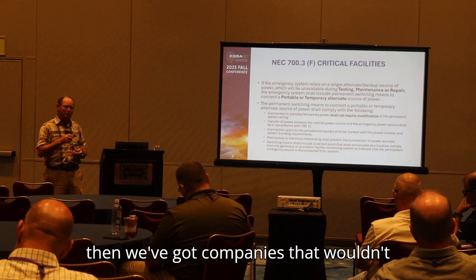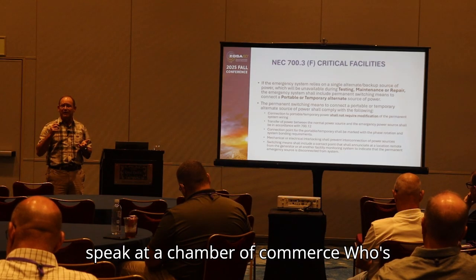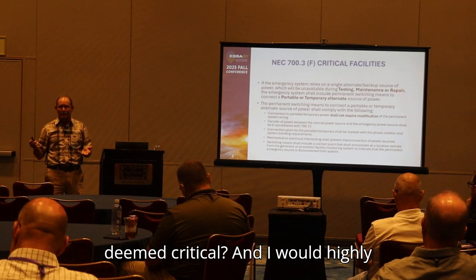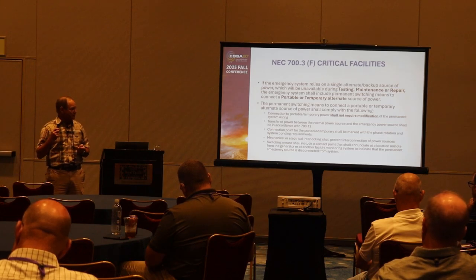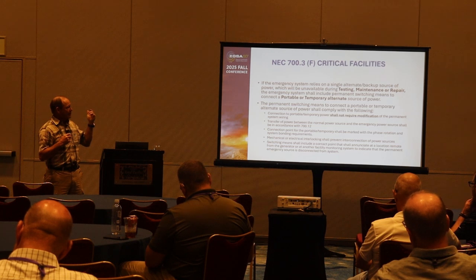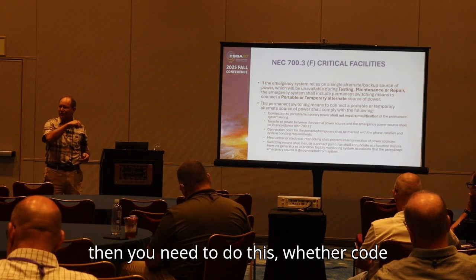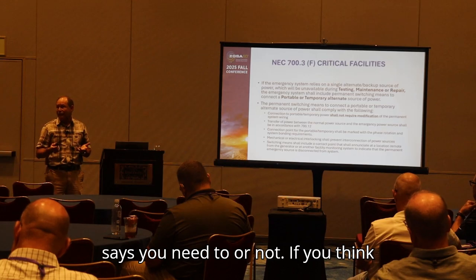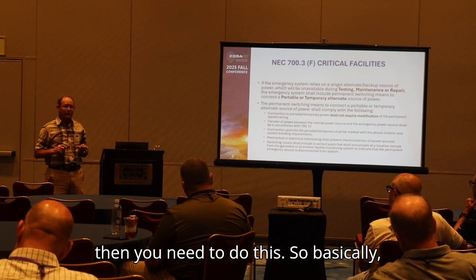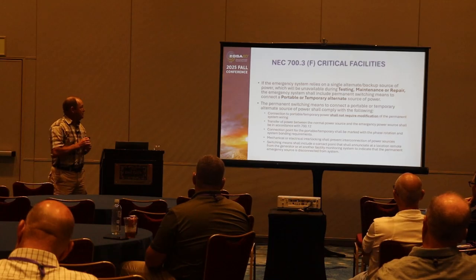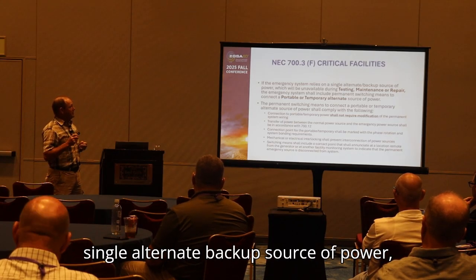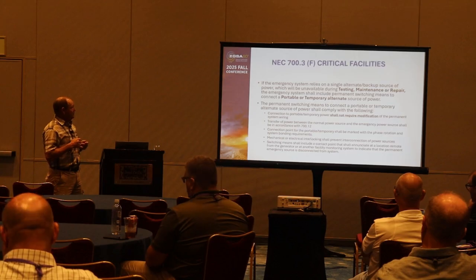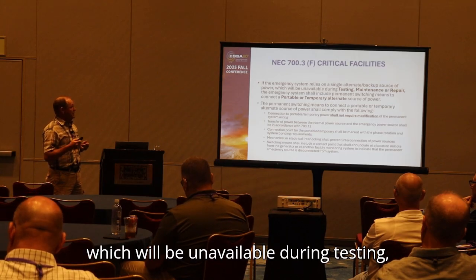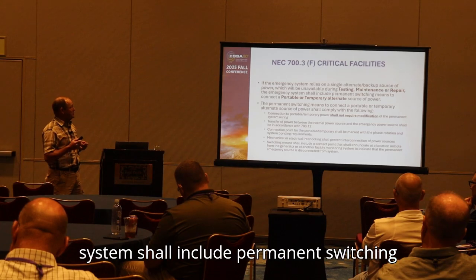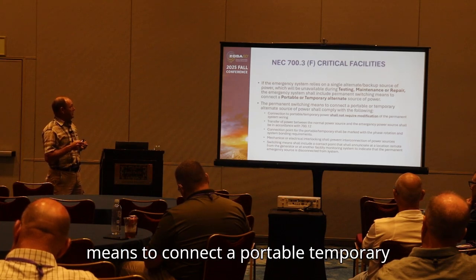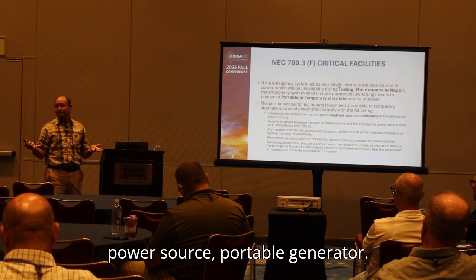And then we've got companies that wouldn't necessarily fall under it, but if you go speak at a Chamber of Commerce on who's deemed critical - and I'd highly suggest y'all do that - they're like, well, I'm critical. Well then you need to do this, whether code says you need to or not. If you think you're critical to that infrastructure, then you need to do this. So basically, if the emergency system relies on a single alternate backup source of power, which will be unavailable during testing, maintenance, or repair, the emergency system shall include a permanent switching means to connect a portable temporary power source - a portable generator.